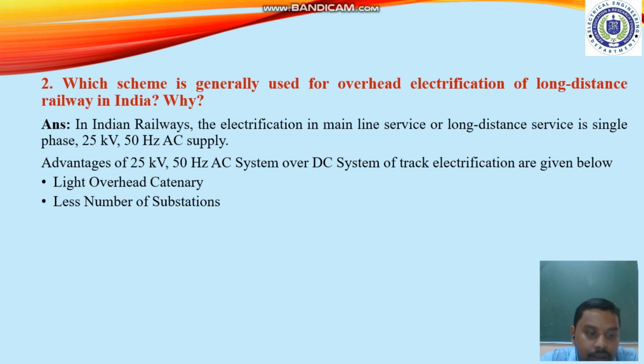In comparison, for 1500 volt DC, the spacing is 5 to 15 kilometers, and for 3000 volt DC, the spacing is 15 to 30 kilometers. So the required number of substations along the track is considerably reduced, leading to substantial savings in capital expenditure on the track.